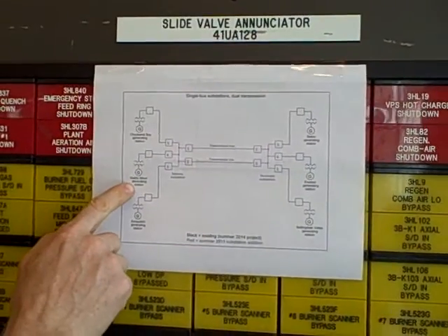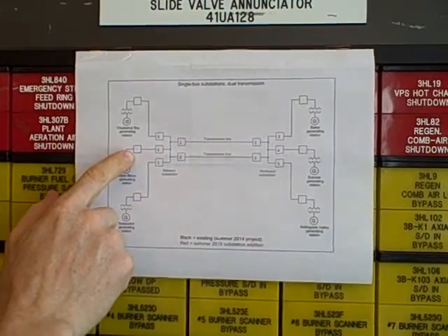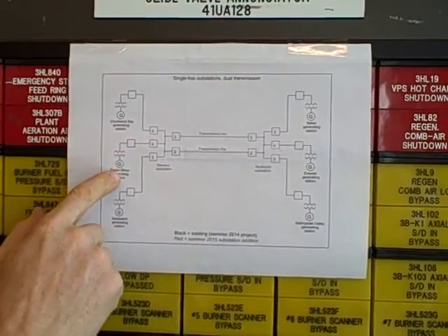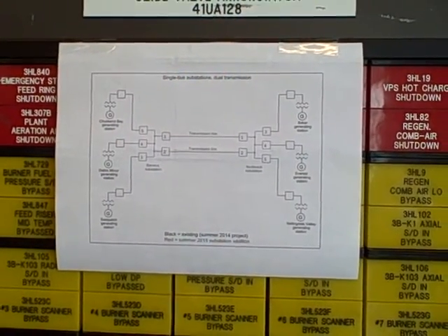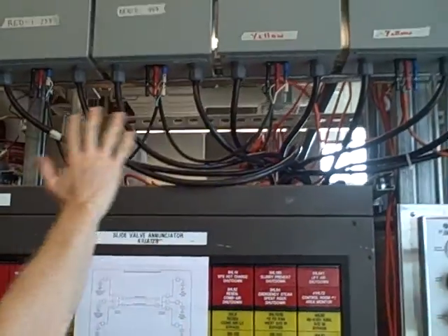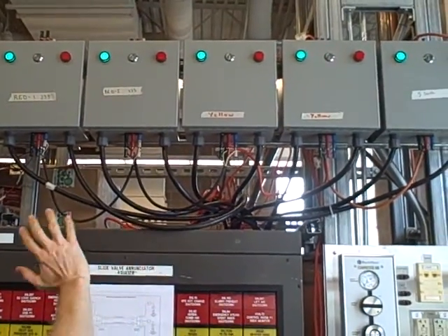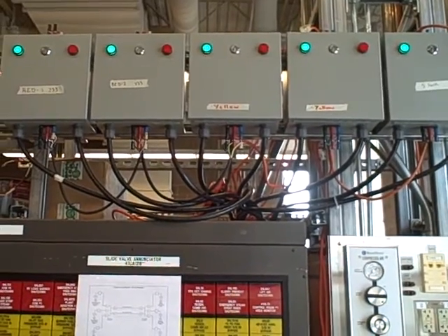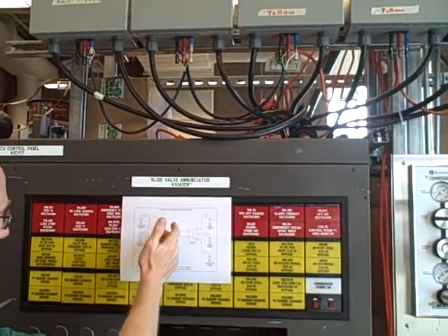So to give you a little bit of background, this is the Stevens substation in our power system. We currently have one generator running. The Diablo Miner generator is running, and its circuit breaker is closed, so it is ready to feed power to our substation. Currently, looking at our breakers, all five of the breakers are open. They're all tripped. They're all green. They're all off. So that means none of that generator's power can get to this bus.